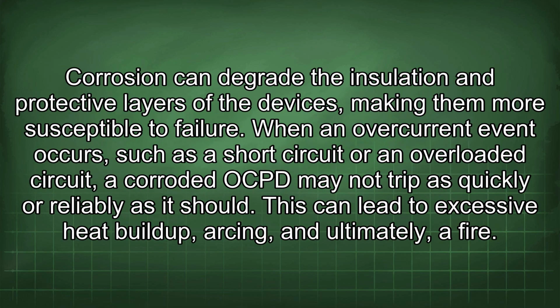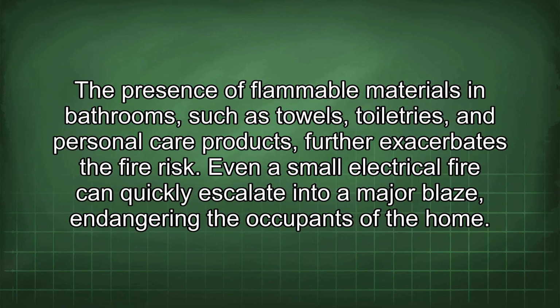Corrosion can degrade the insulation and protective layers of the devices, making them more susceptible to failure. When an overcurrent event occurs, such as a short circuit or an overloaded circuit, a corroded OCPD may not trip as quickly or reliably as it should. This can lead to excessive heat buildup, arcing, and ultimately a fire. The presence of flammable materials in bathrooms, such as towels, toiletries, and personal care products, further exacerbates the fire risk. Even a small electrical fire can quickly escalate into a major blaze, endangering the occupants of the home.